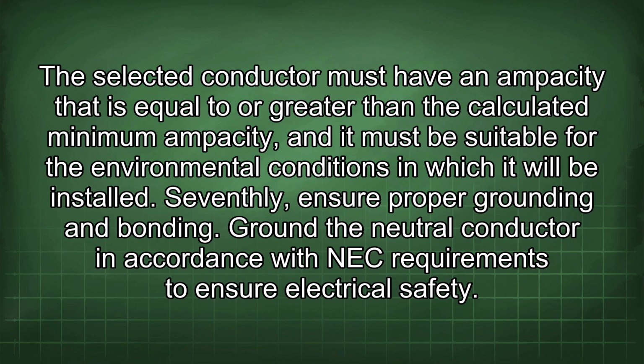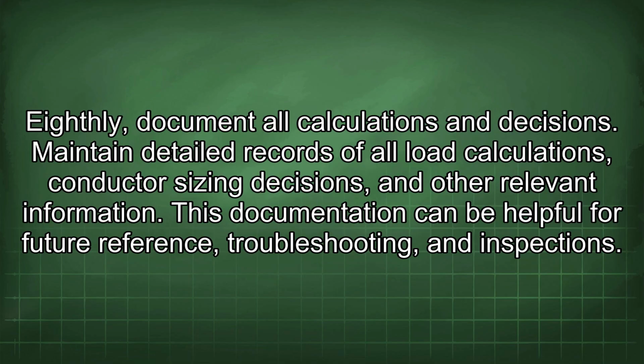Seventhly, ensure proper grounding and bonding. Ground the neutral conductor in accordance with NEC requirements to ensure electrical safety. Eighthly, document all calculations and decisions. Maintain detailed records of all load calculations, conductor sizing decisions, and other relevant information. This documentation can be helpful for future reference, troubleshooting, and inspections.